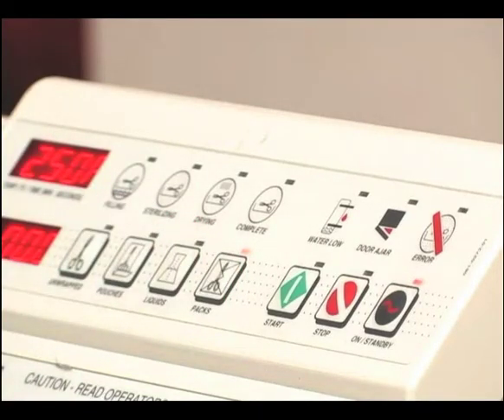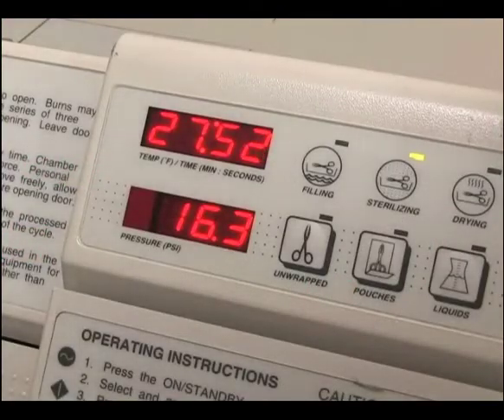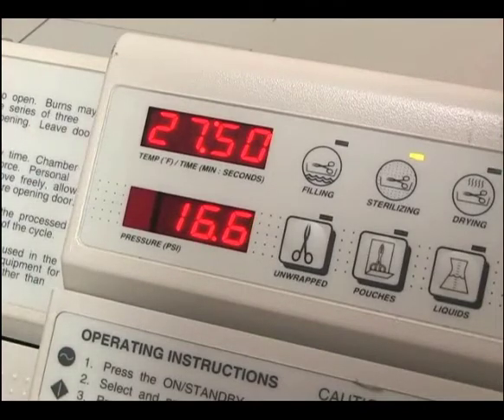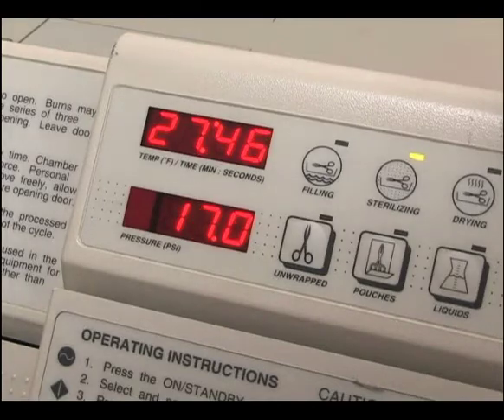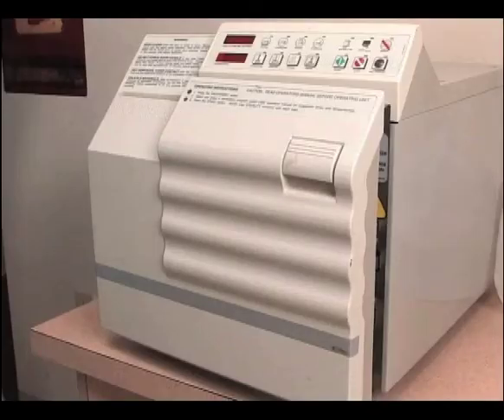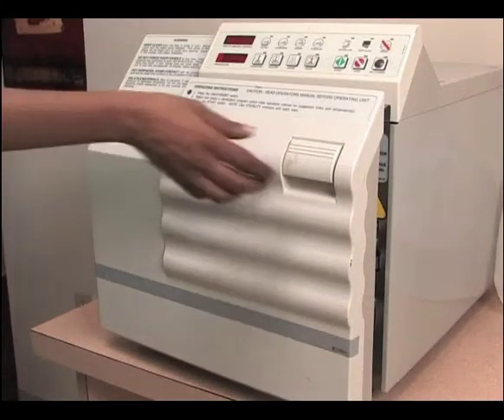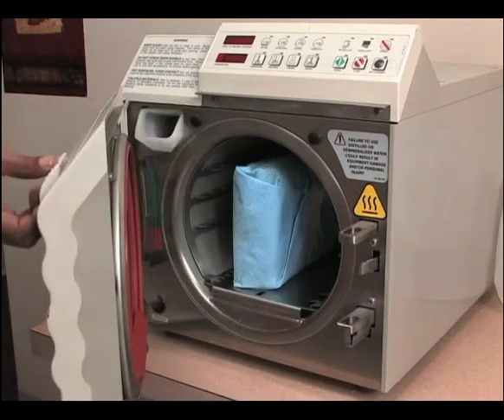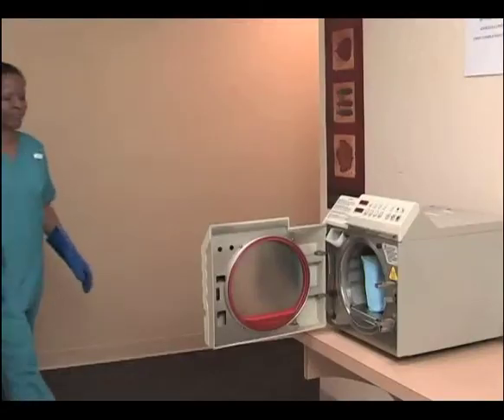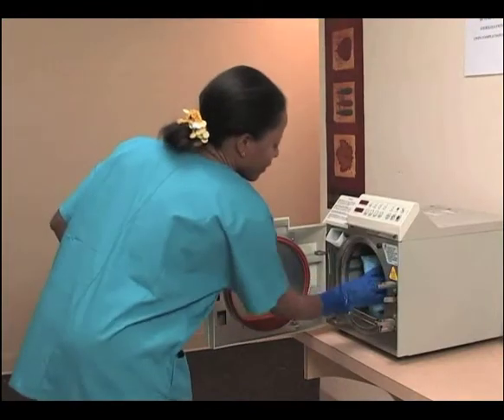Sterilization time begins when the correct pressure and temperature have been reached. Once the sterilization process is complete, ensure that steam pressure has been manually or automatically released. Next, open the autoclave door slightly to allow the load to air dry. Larger packs with dressings may take 45 to 60 minutes to dry. Wearing heat-resistant gloves, remove the dry packages.